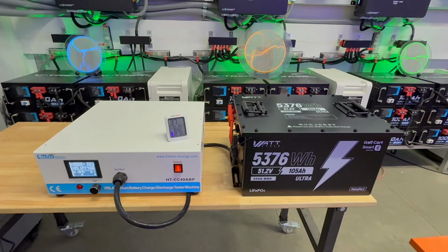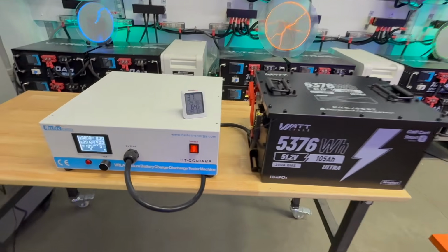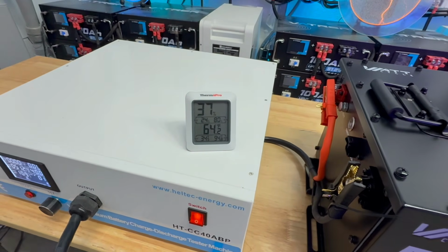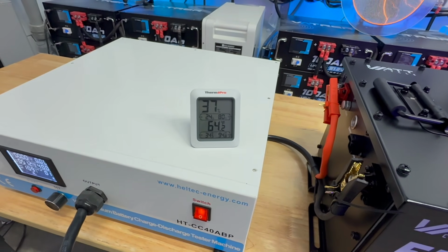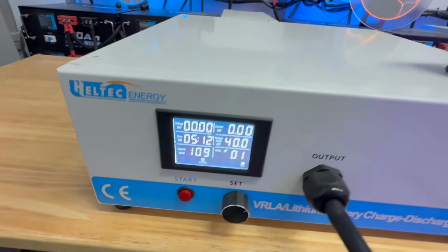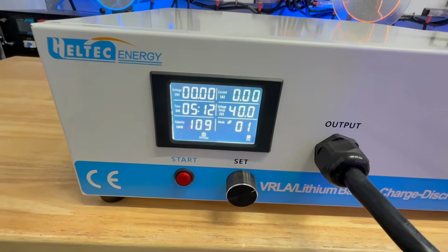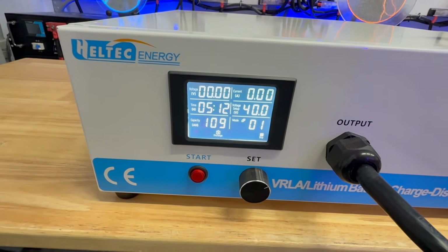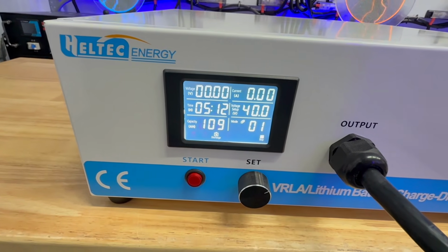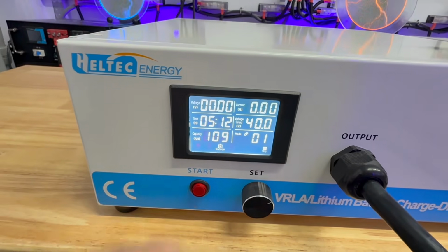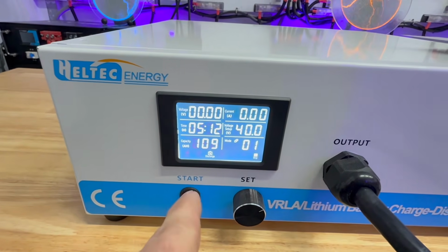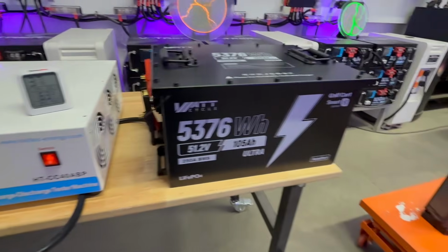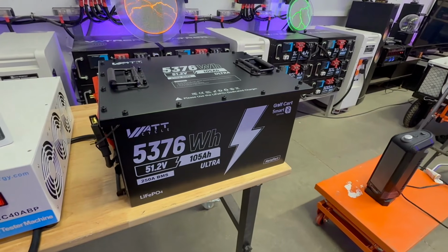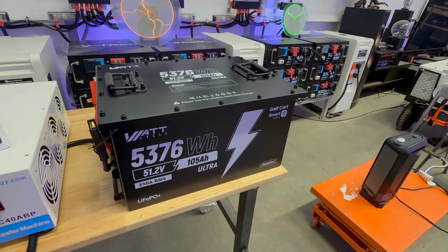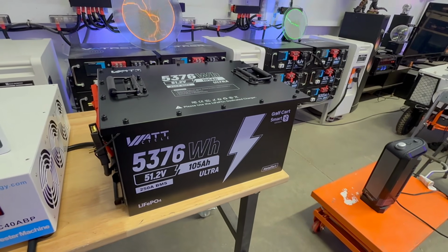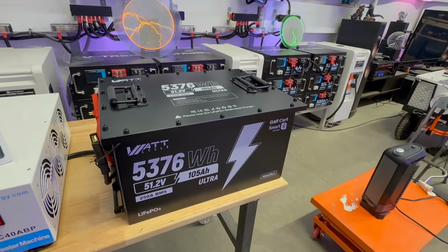Now that the battery capacity test is complete, let's see how it did. One thing to note, the temperature in my shop is 64 degrees, so that may affect the capacity slightly. Here's what it ended up being: I have the low cutoff at 40 volts, could probably do 39, but 40 should be empty. With that, it ran for 5 hours and 12 minutes, and it pulled 109 amp hours. So for a battery rated 105 amp hours, 109 is good, especially not testing at the optimal temperature and having the cutoff set on the tester.